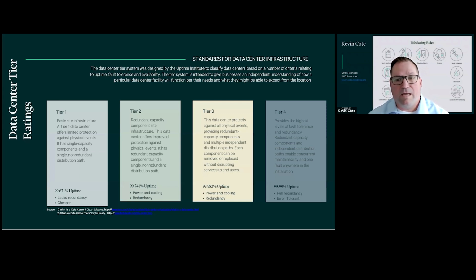If you have tier 1 and something happens, you go down. With tier 2 and some redundancy, expected downtime is 22 hours per year, for 99.741% uptime. For tier 3, allowable downtime is 1.6 hours annually. Tier 4 is 26 minutes annually. That's the difference between 99.671% and 99.99% uptime.